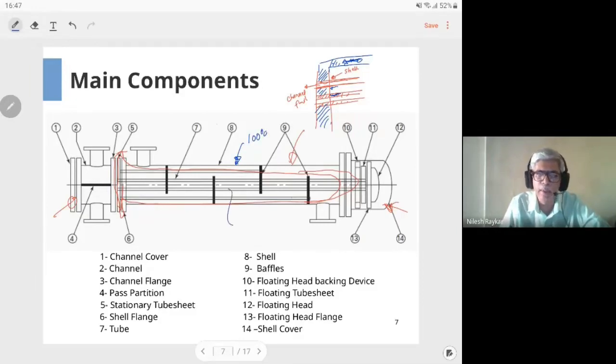And the tubes, let's say it is a boiler, so the gas inside has an average temperature of 200. So the tubes will expand more than the shell. And the tube sheet is the one which connects these two components to each other. So the tubes are sort of getting clamped by the colder shell, and that effect needs to be considered, and that load gets transferred to the tube sheet. So that needs to be taken into account.